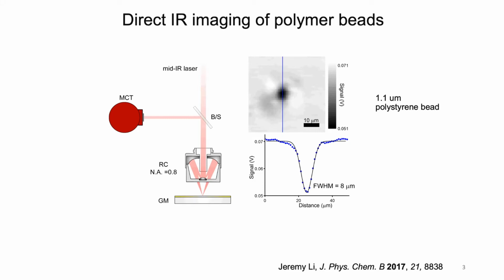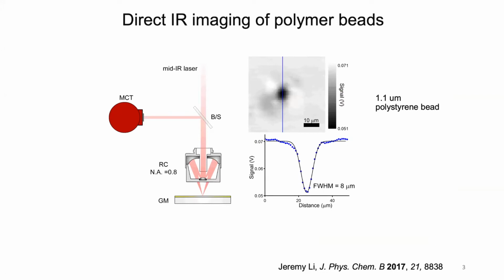In this experiment, our spatial resolution was about 8 microns, which is actually worse than what you would expect based on the diffraction limit. This is about a 3 micron light experiment, so you'd expect to get maybe about a 2 micron spatial resolution. We're a lot worse. And this is another problem you have in the IR: Cassegrain objectives are really pretty difficult to use, and in our hands, that's as good as we could do. So we really don't like Cassegrains. They're a bit of a mess, and they don't give you great resolution, certainly not near what one might expect. So those are the problems with directly imaging in the IR.